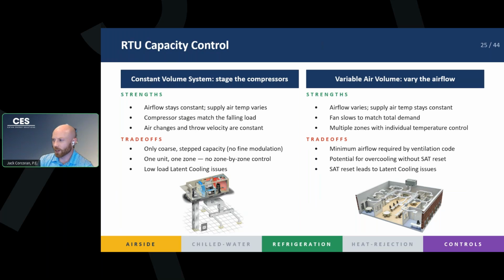Of course, the trade-off that we're going to have here is you can't modulate it down to zero. There's a minimum airflow per code to every zone based on the number of people and the square footage. So if you have a high outside air requirement in each zone, your minimum airflow, right? You're going to only be able to turn down to the minimum. It might be 50 to 70% of your zone airflow is going to be required. So you're going to be overcooling that space pretty often, if you don't have another way to reheat it, or maybe you didn't separate it out from the rest of the system. So your minimum airflow based on outside air always has to be considered.